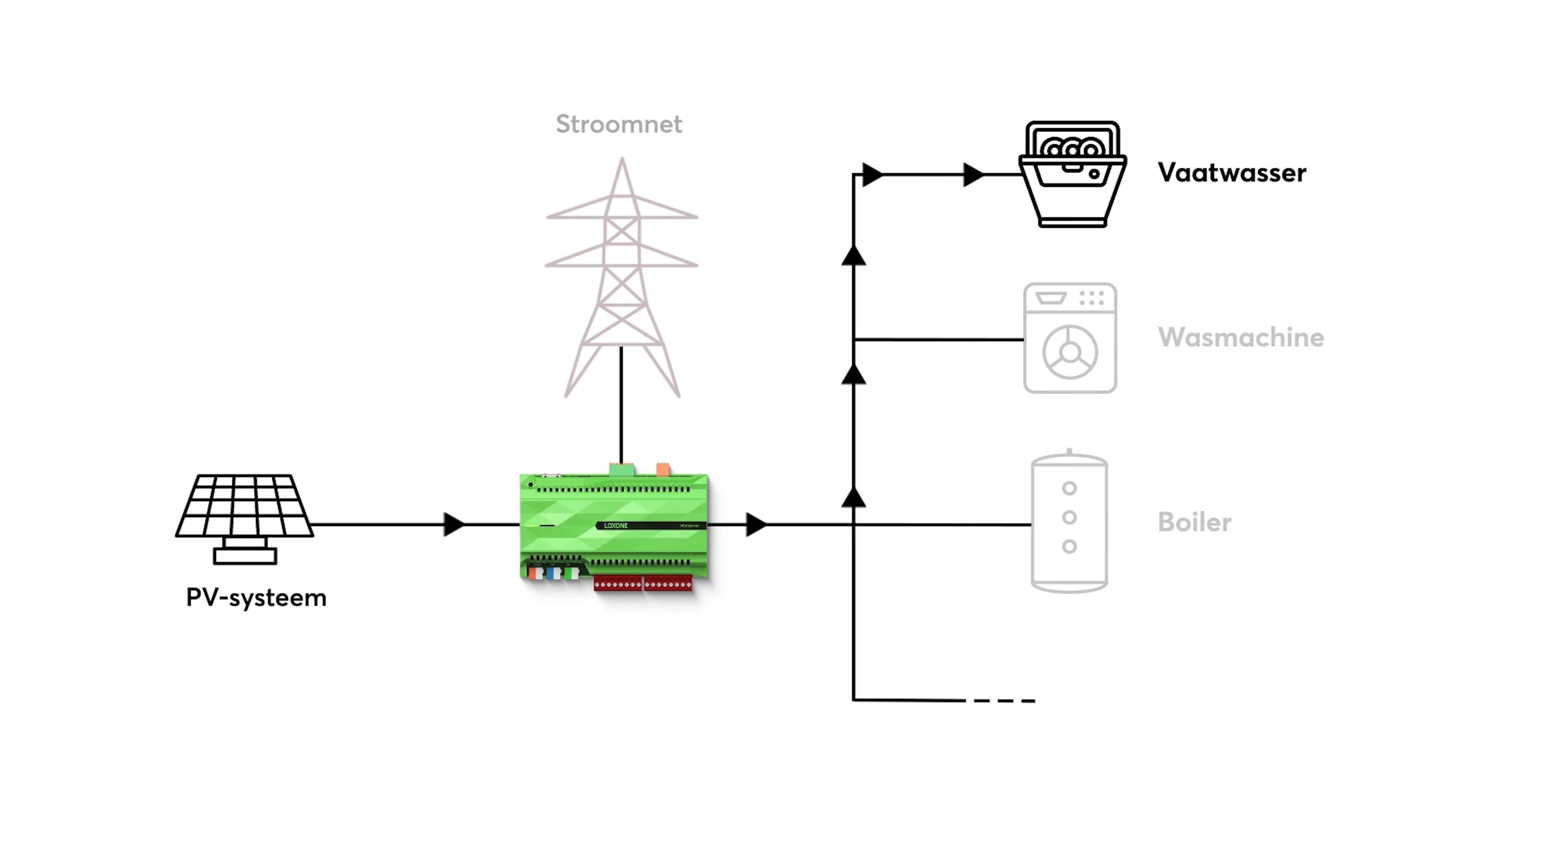The Loxone Mini Server and the specially developed Energy Manager function block help you achieve this very task. You can use the function block to control up to 12 electrical devices. So if more energy is being produced than is currently being consumed, rather than this energy going back into the grid, it can be intelligently directed to the selected devices based on load and priority.